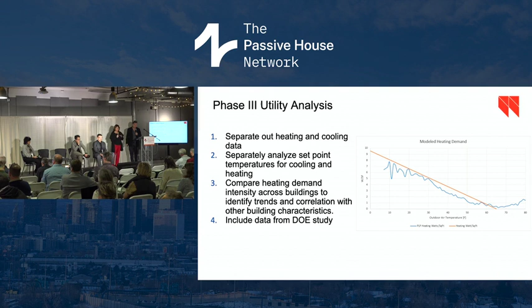Agreed. So now that we have this data and we've been struggling with it and wrestling it to the ground, what's our next step? Phase 3 of our utility analysis is going to be looking more closely at that balance point for heating, for the heating demand. Where are we actually seeing the heating energy come onto the building? So we're going to evaluate different base loads under which we think heating is - we started with 55, we're going to go to 50, 45, and 40.